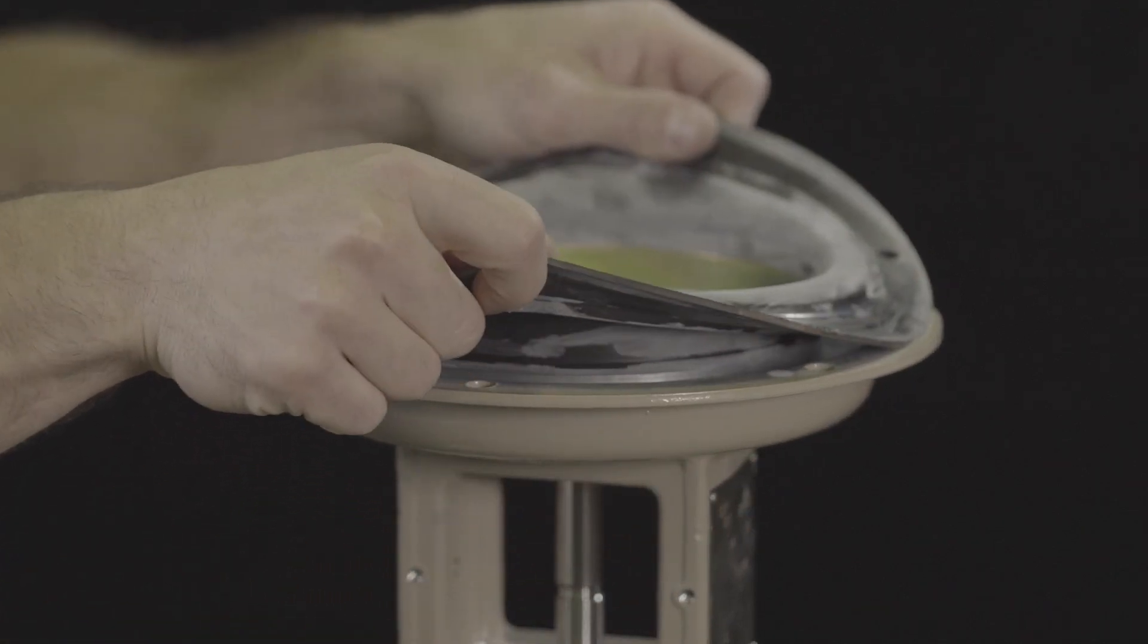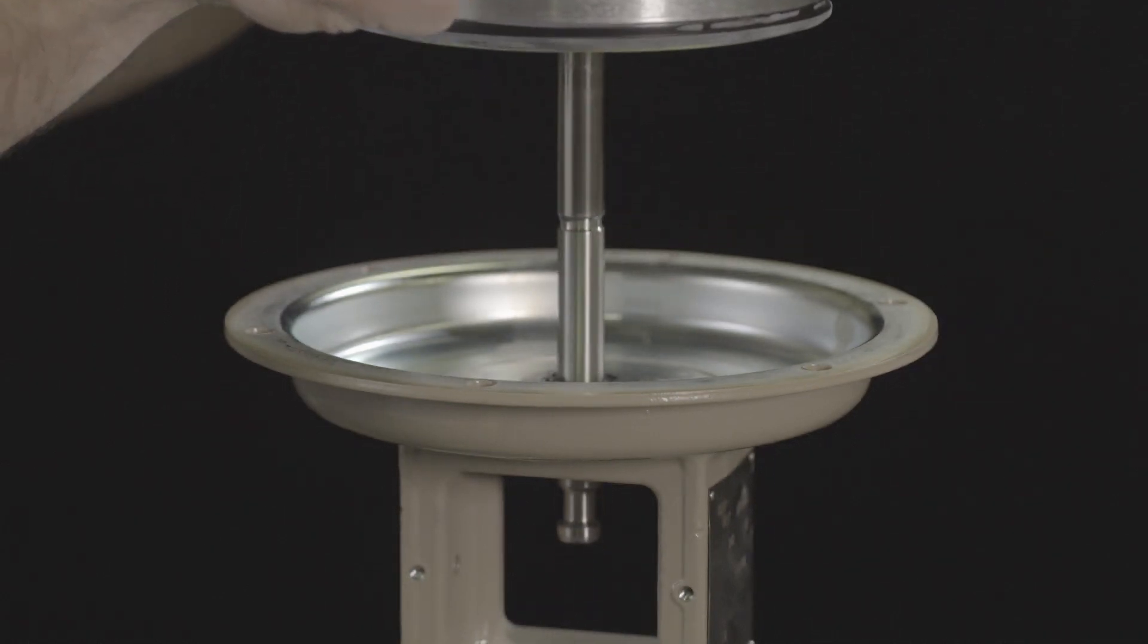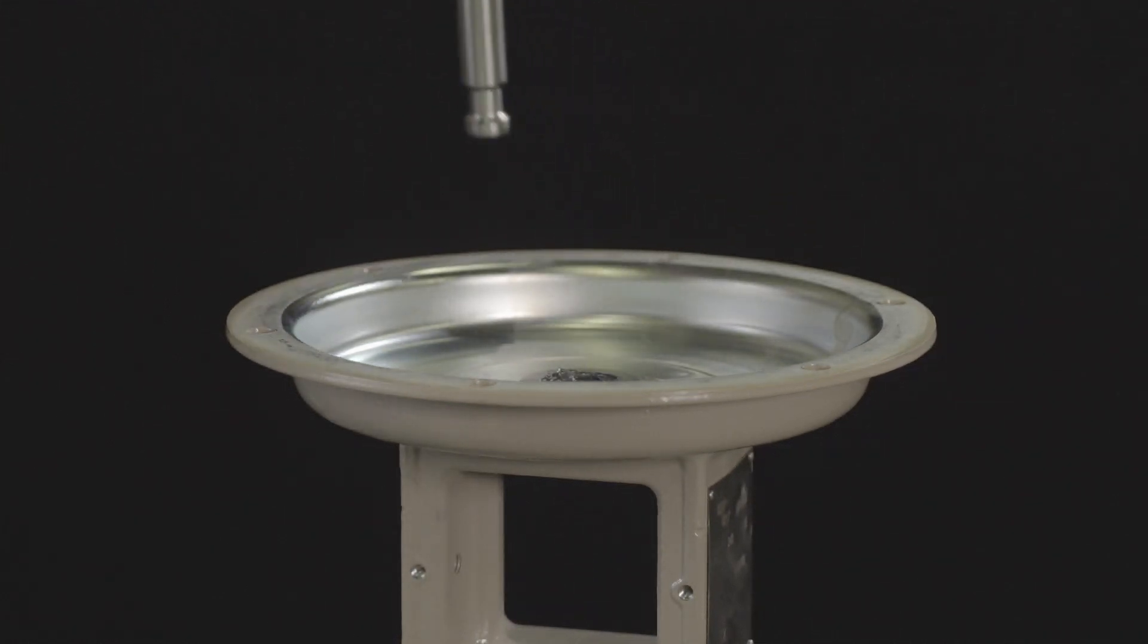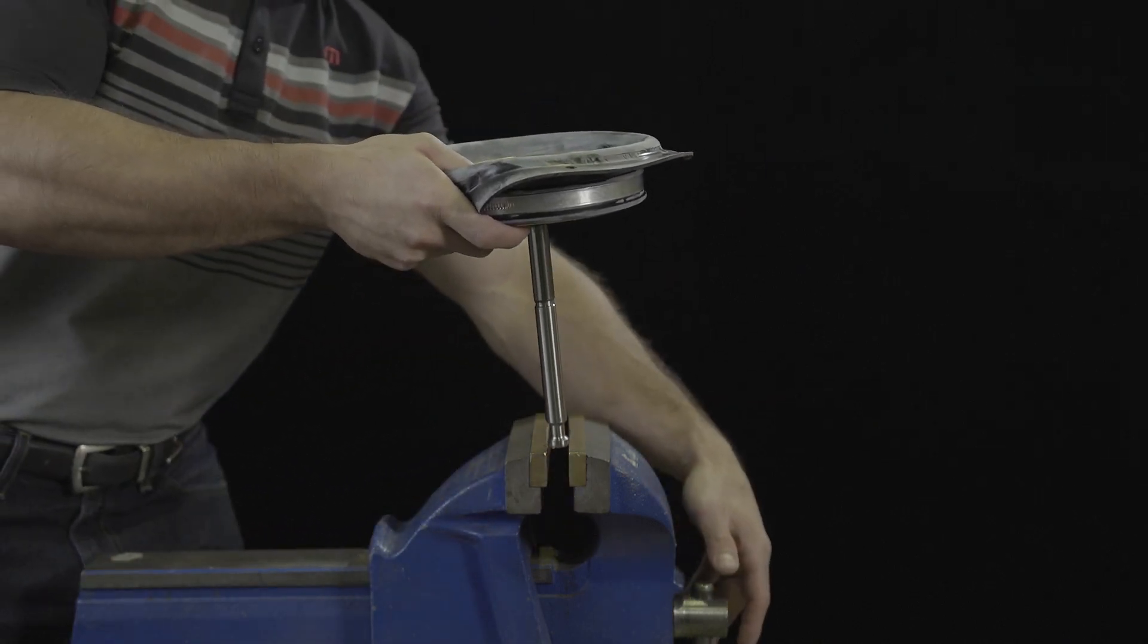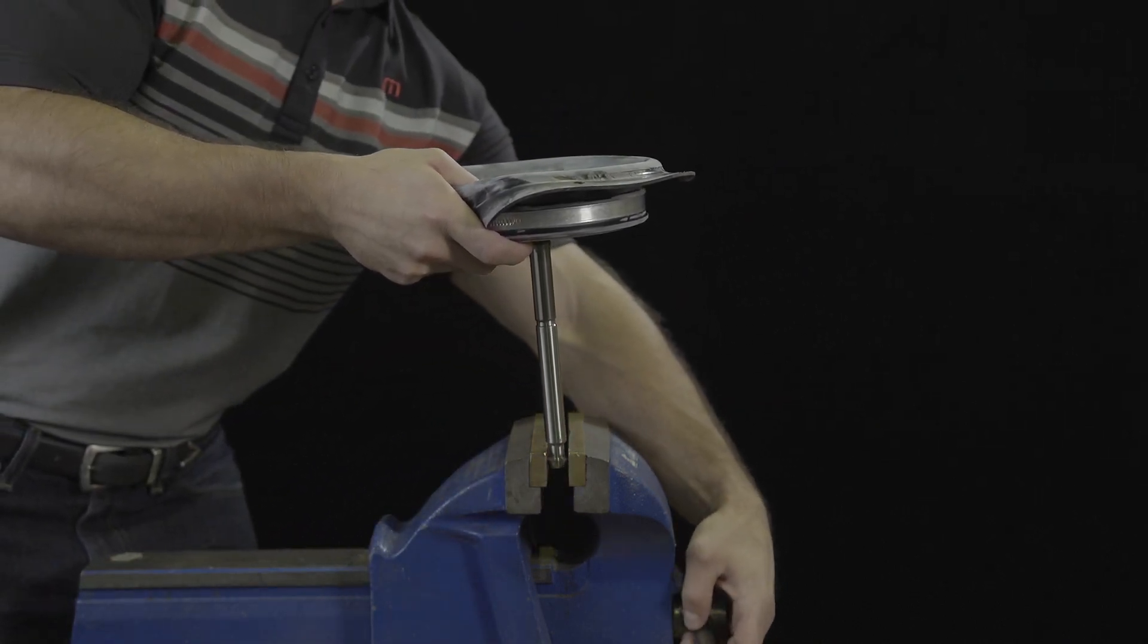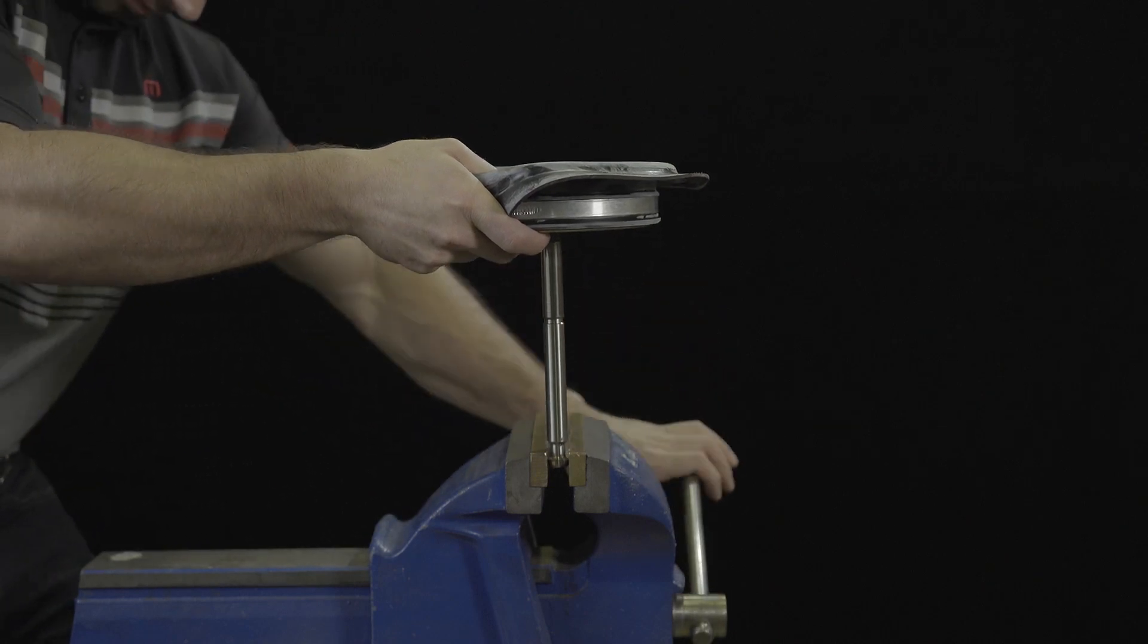Pull the diaphragm plate assembly consisting of the diaphragm plate, diaphragm, and actuator stem out of the bottom diaphragm case. Clamp the bottom section of the actuator stem into a vise using protective jaws ensuring the actuator stem is not damaged.